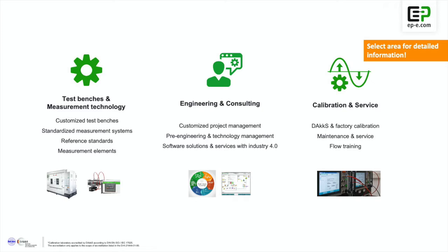Last but not least, calibration and service. This is very important, especially for you as a customer, because after purchasing from us, after 1 year you need to ensure the precision is still there. Your quality assurance department will ask after 1 or 2 years how you know the airflow conditioning or airflow measurement machine is still in range. We offer calibration service across Europe, from EP Germany in Niederstetten, and in Asia with EP China in Hangzhou.